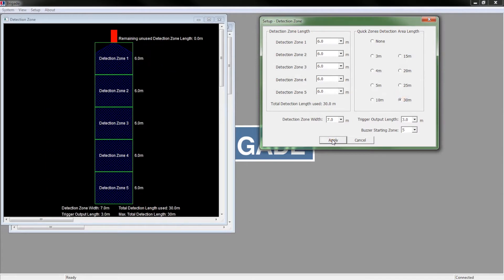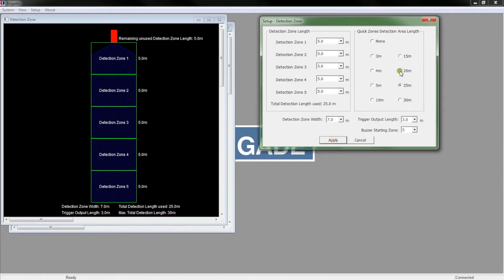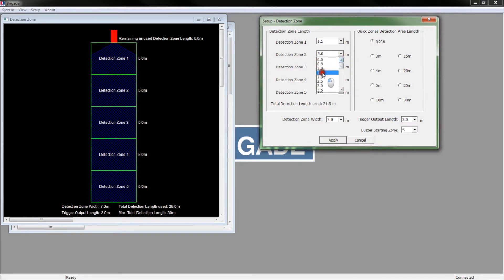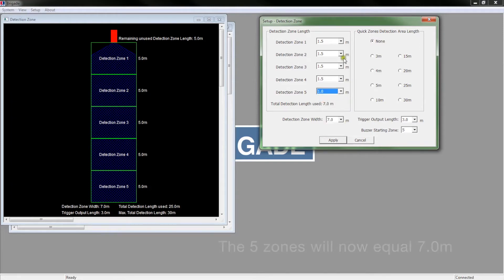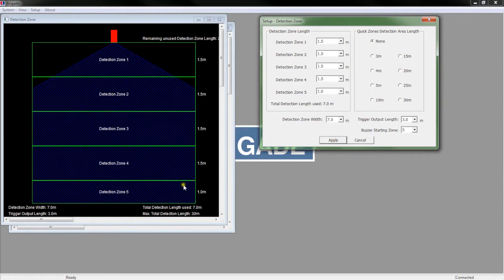In this example, my customer has chosen a 7m detection length in increments of 1.5m, with the outer zone set to 1m. Select the indicator. Each detection zone length can be selected using the drop-down menus here. When the detection length is increased, the tool will automatically widen the detection zone. The width should be 7m, and the detection zone width is set here. When you have selected the required width, click Apply.